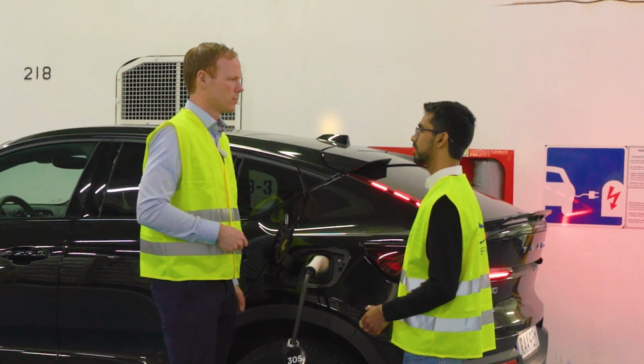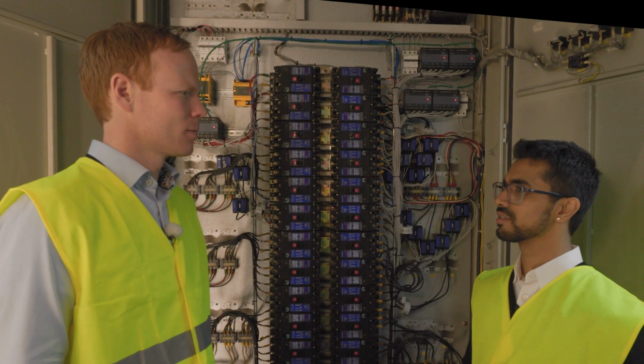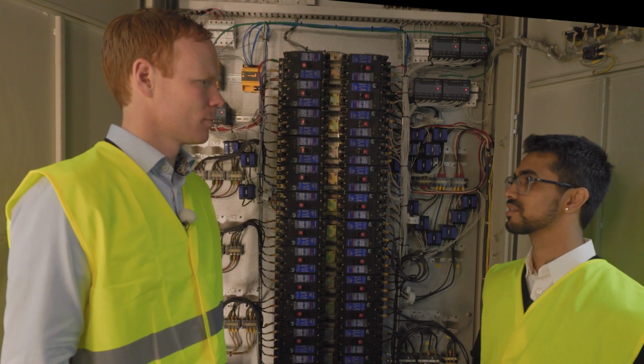All the electrical connections to EVs that are charging and reefer units that are powered are constantly monitored by energy meters, insulation fault locators, and insulation measurement units. Every time there is a deviation from the norm or an anomaly is detected, the independent unit can either be disarmed manually or from the bridge. The key benefit of this solution is that an alarm is raised before there has been any actual damage or a fire situation has occurred on board.